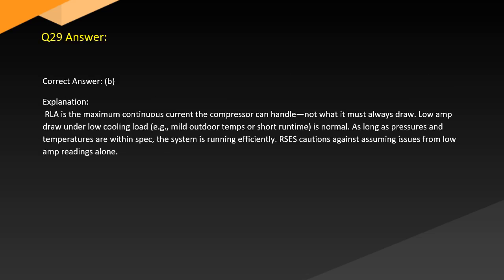Answer. Correct answer, B. Explanation. RLA is the maximum continuous current the compressor can handle, not what it must always draw. Low amp draw under low cooling load, e.g. mild outdoor temps or short runtime, is normal. As long as pressures and temperatures are within spec, the system is running efficiently. RSES cautions against assuming issues from low amp readings alone.